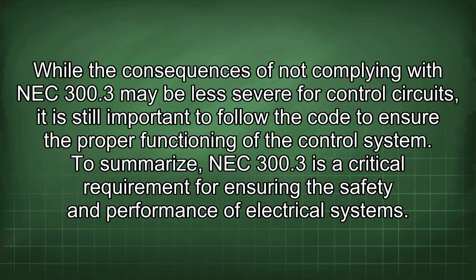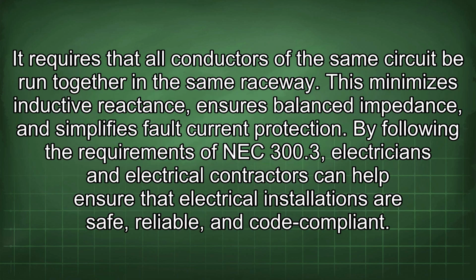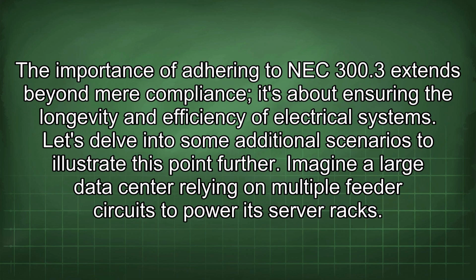To summarize, NEC 300.3 is a critical requirement for ensuring the safety and performance of electrical systems. It requires that all conductors of the same circuit be run together in the same raceway. This minimizes inductive reactance, ensures balanced impedance, and simplifies fault current protection. By following the requirements of NEC 300.3, electricians and electrical contractors can help ensure that electrical installations are safe, reliable, and code compliant. The importance of adhering to NEC 300.3 extends beyond mere compliance. It's about ensuring the longevity and efficiency of electrical systems.